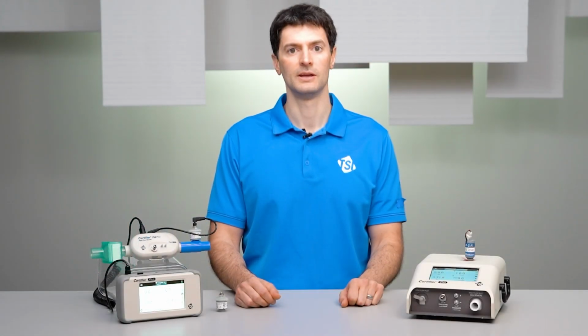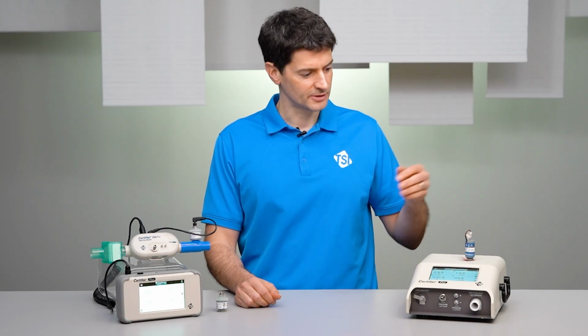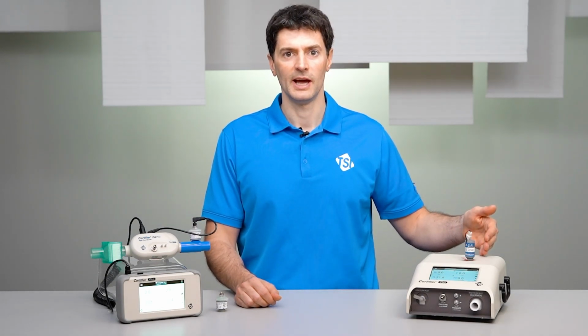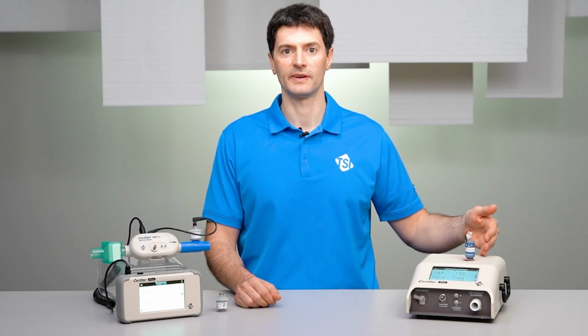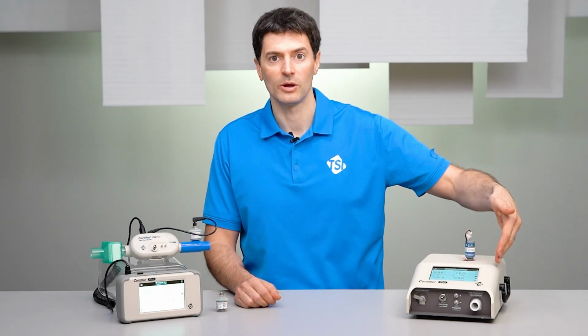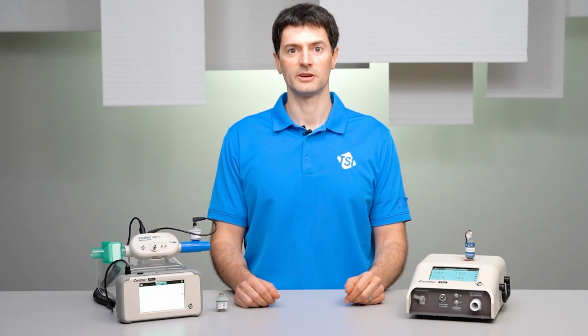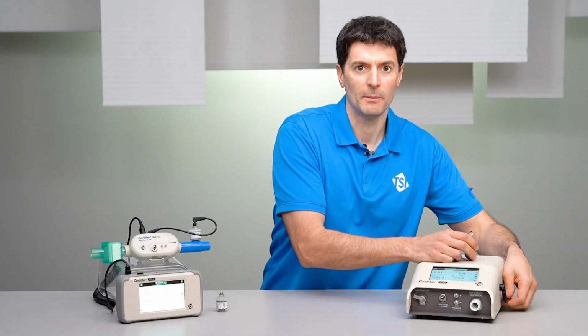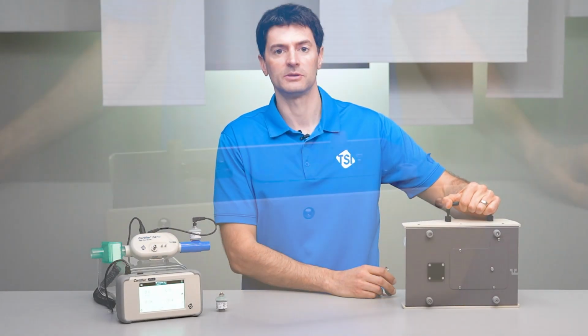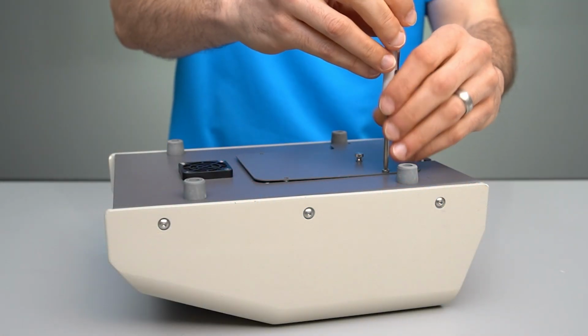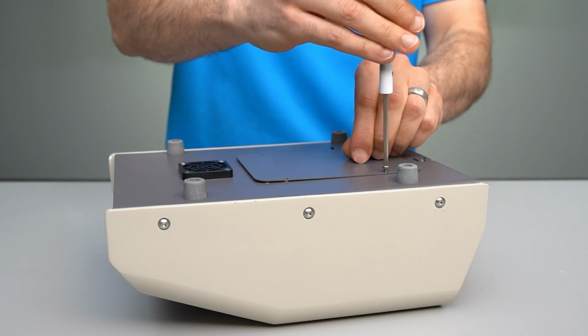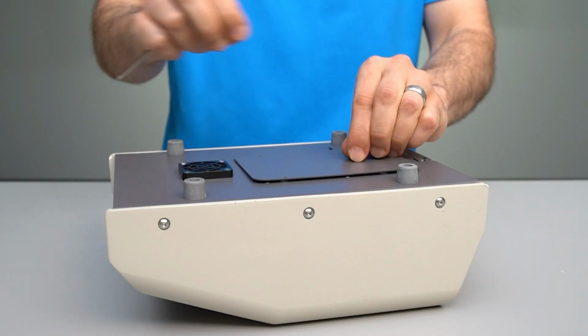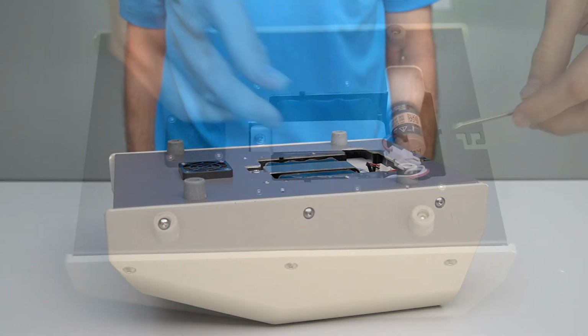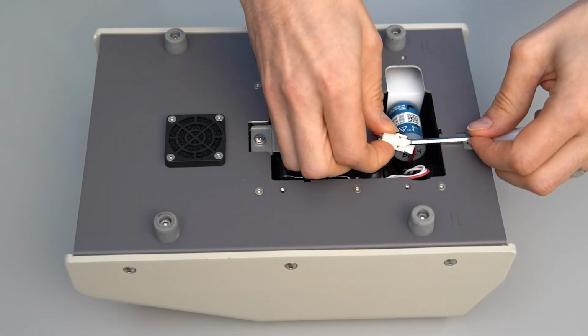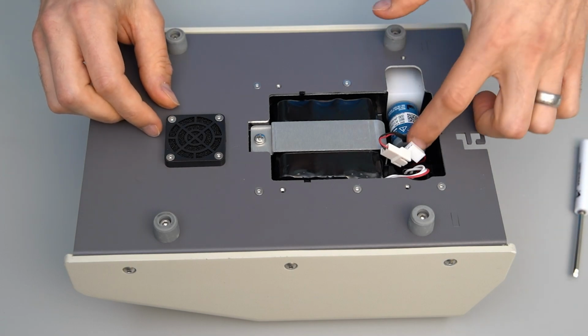module. For the Certifier Pro model, the oxygen sensor is integrated into the instrument and measures the oxygen concentration of gas flowing through the high flow channel. The sensor can be accessed by removing the bottom cover on the Certifier Pro. To replace the oxygen sensor, after removing the bottom cover, disconnect the pigtail connector, then retract and unscrew the sensor cell.